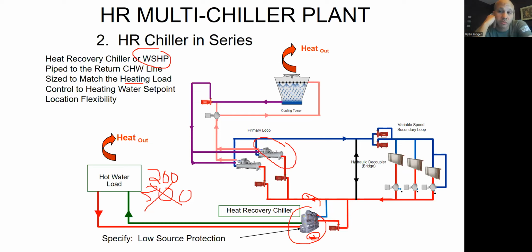The cool thing about those water source heat pumps for individual tenants like that is some tenants can take heat off of that loop, and different tenants can put heat onto that loop. So if you're in the interior, you're dumping heat onto the loop. And if you're in the perimeter in the winter, you're taking heat off of that loop. And if I take 2 tons of heat off and you add 2 tons of heat, I don't have to run a boiler or a cooling tower, right?